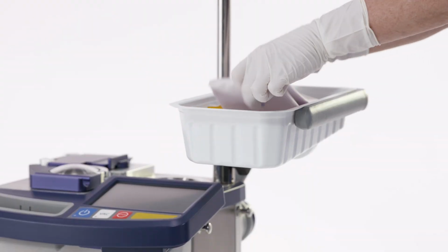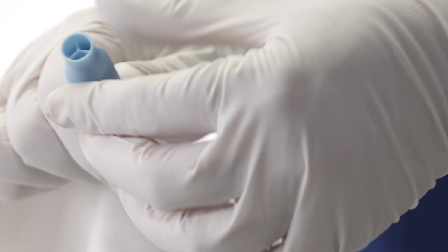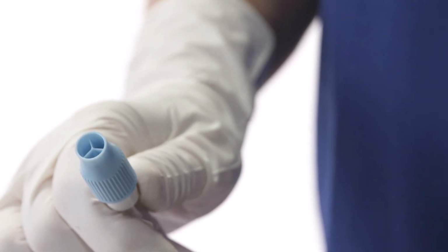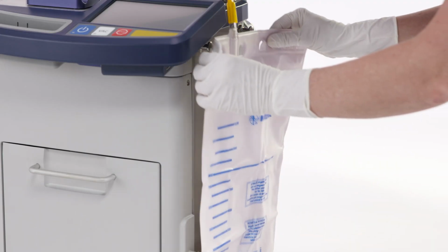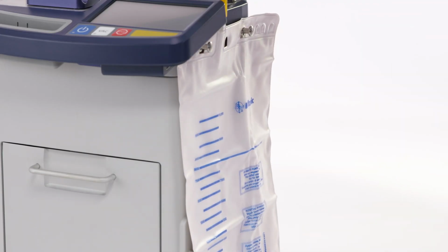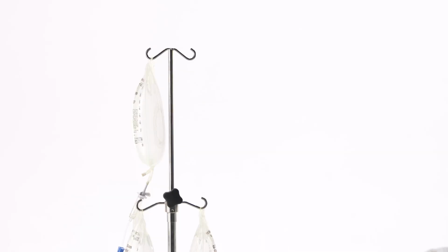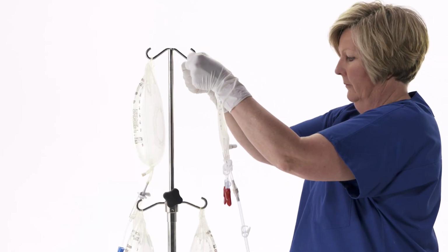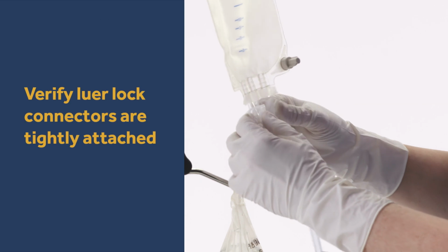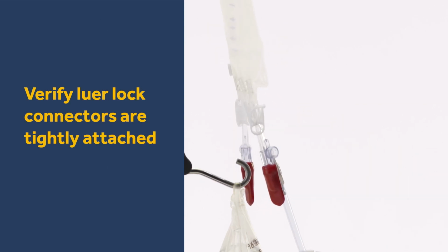Remove the waste bag from the wash kit and make sure that the drain valve on the waste bag is closed. Next, install the waste bag onto the waste bag pins. Remove the holding bag from the wash kit and hang it on an upper IV pole hook. Then close the clamps on the two red-capped outlet lines that each include a membrane port.